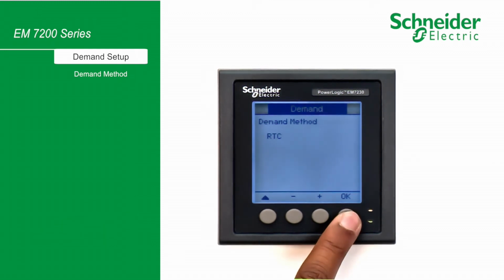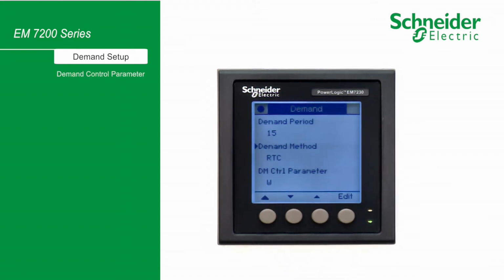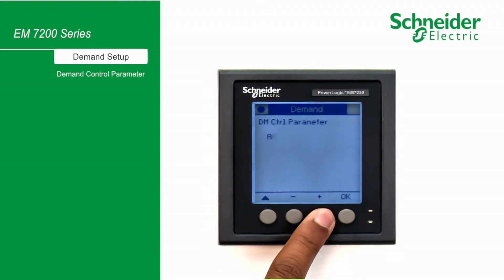Press OK. Your demand controller has the option of selecting different demand computing parameters: active power, apparent power, and three-phase current average. Please note that VARH is not the option for demand controlling, although you can view the demand computation in the meter display. Let's select VA, then press OK.